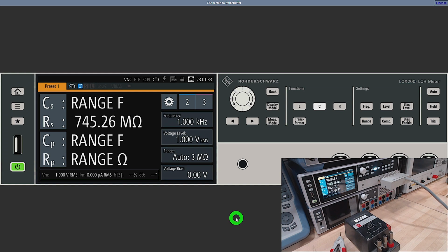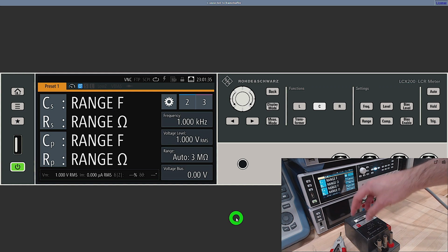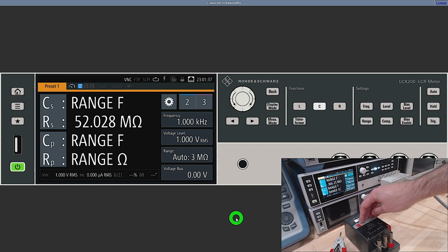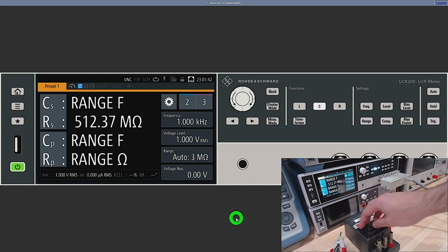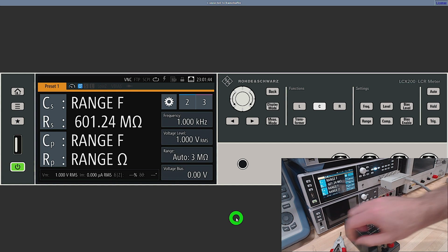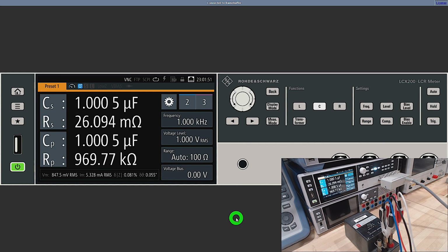So let's first measure something that we really understand. This is a capacitor standard box. It's a 1 microfarad, 0.05% tolerance. So it's very accurate and it's been calibrated already, so I know the value exactly. Let's go ahead and plug it in, and we should see a result very, very close to that. Look at that, 1.0005 microfarad.